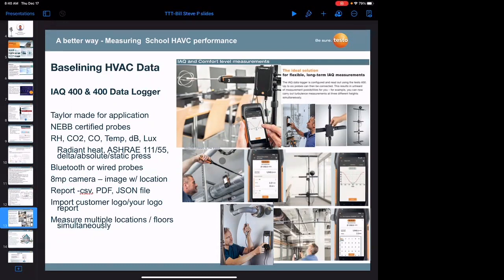While you can take this unit up to the mechanical penthouse or the supply and exhaust flow areas of the main mechanical system, do your duct traverses, measure your pressure drop across the filter assembly, measure the external static pressure at the air handler, all the variables that are needed and actually done at the beginning when the system was designed and installed. Another cool aspect is that the 400 has a number of ASHRAE protocols already built into it.